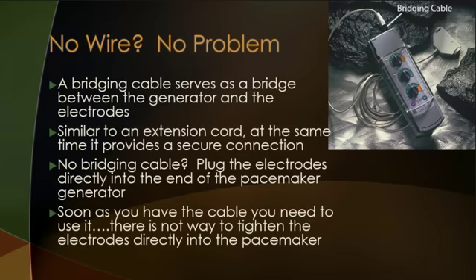So I kind of said something about this earlier, but no wire, no problem. A bridging cable serves as a bridge between the generator and the electrodes, and it really does a great job if you tighten the screws on the side enough, tightening down and securing those electrodes. The bridging cable is just similar to an extension cord, so at the same time it provides a secure connection. If you don't have a bridging cable, you can plug the electrodes directly into the end of the pacemaker generator. As soon as you have the cable, use it. There's no way to tighten electrodes directly into the pacemaker, so the bridging cable is a lot more secure.